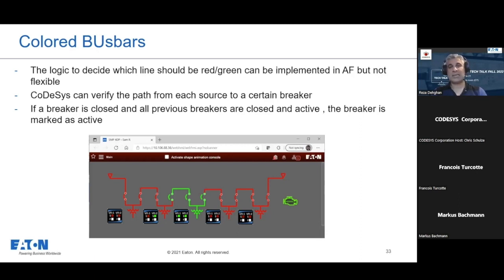And then in the HMI, because even in the HMI we can put some simple logics. In the HMI, we'll say if the right breaker and the left breaker are both closed, show this in red. Again, if one breaker on one of the sides is closed, turn it to red. It means that the line is energized. And if both of the breakers on the two sides of the section are open, then show it in green, meaning that the line is not active or not energized.